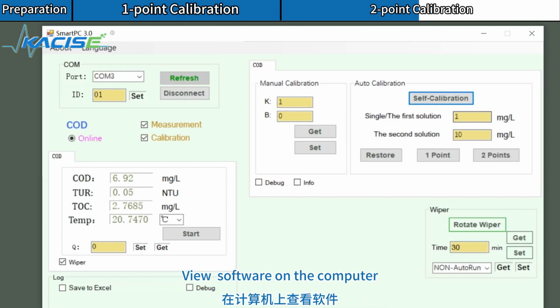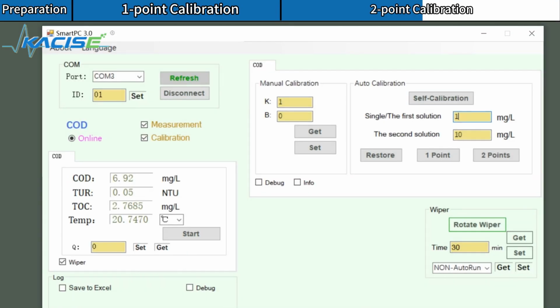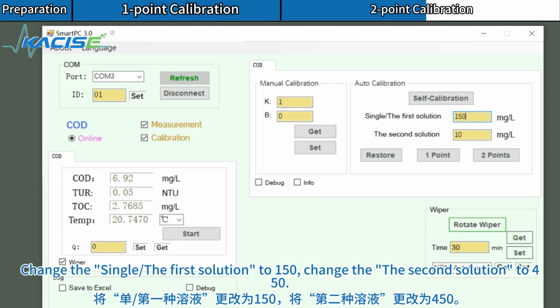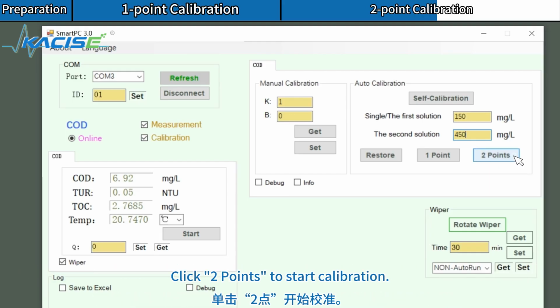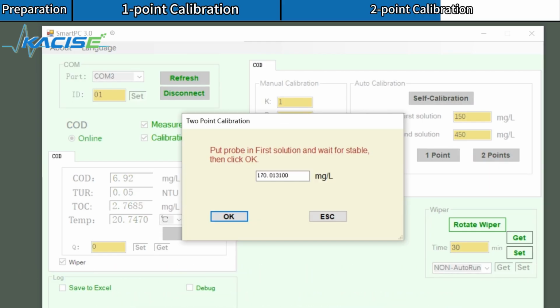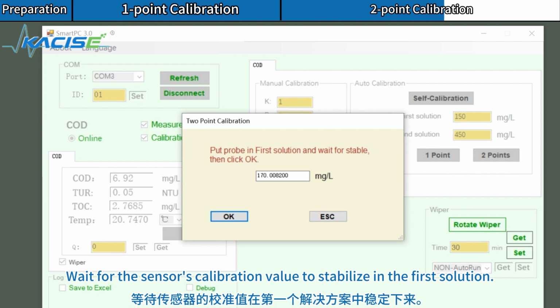View software on the computer. Change the first solution to 150. Change the second solution to 450. Click 2 points to start calibration. Wait for the sensor's calibration value to stabilize in the first solution.